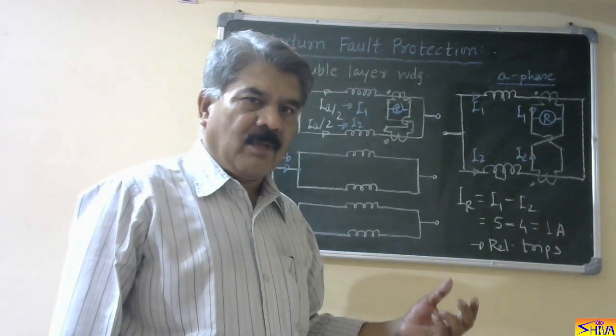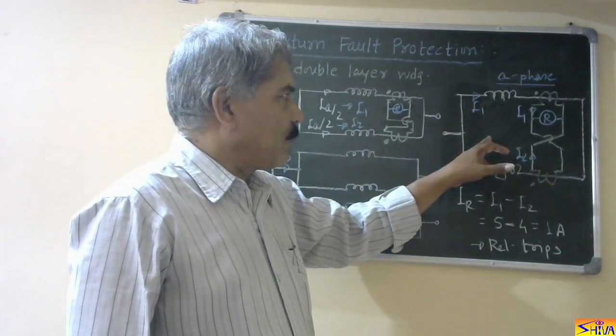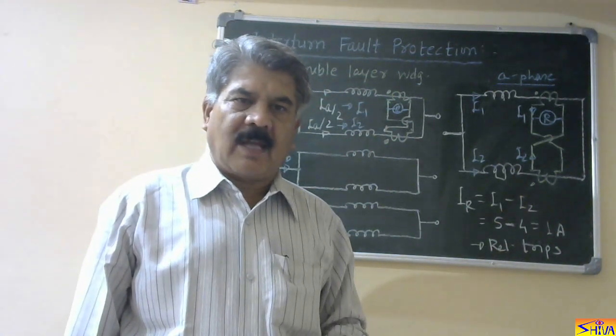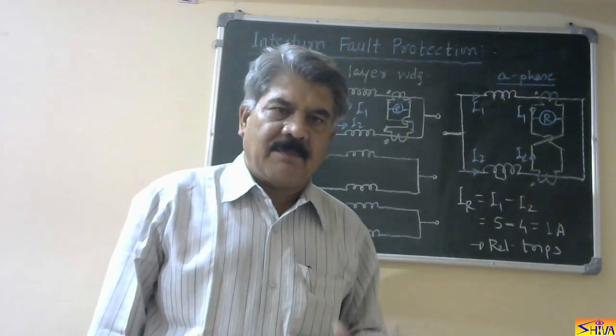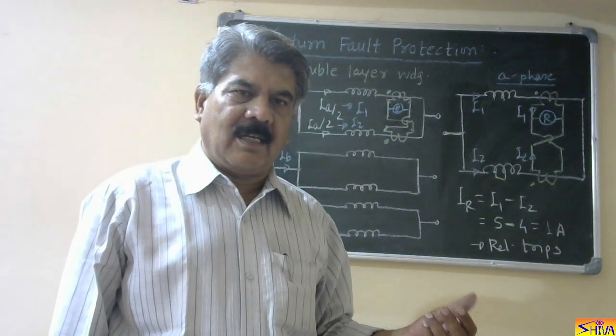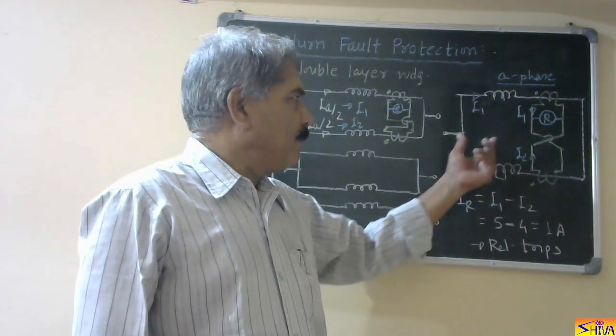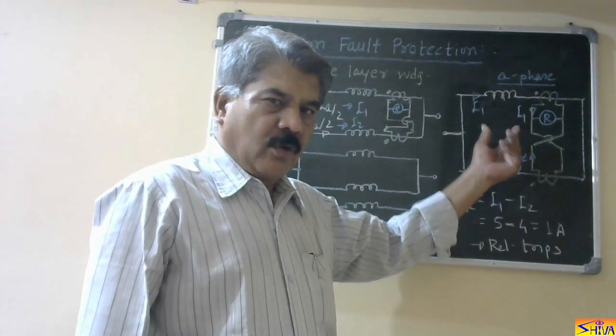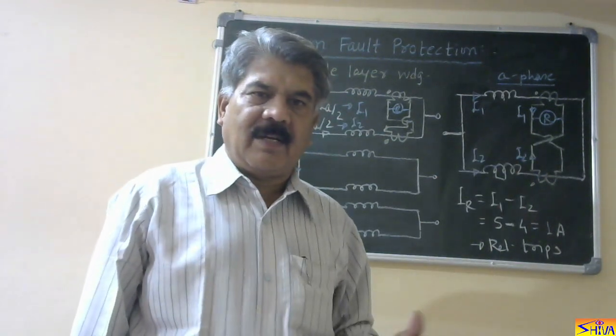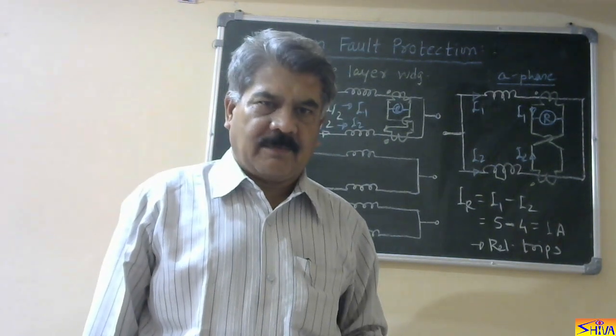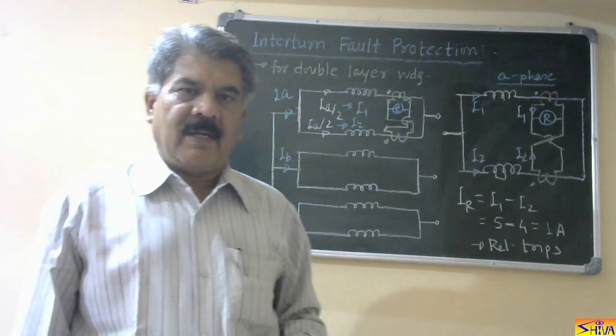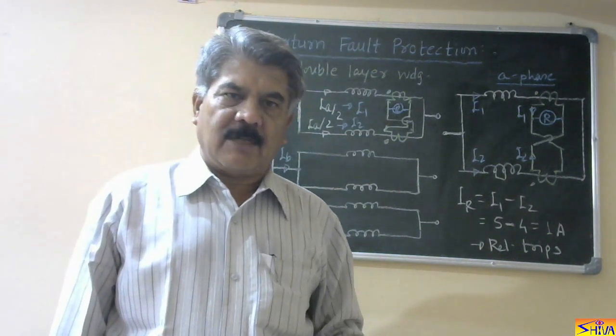For inter-turn faults, we need cross-differential protection or protection using a star open delta type transformer. The star open delta scheme detects inter-turn faults for both single-layer and double-layer winding. However, if we want to use cross-differential protection, it requires double-layer winding. For single-layer winding, the star open delta transformer scheme is used. This covers all inter-turn fault protection for the stator winding of the generator.